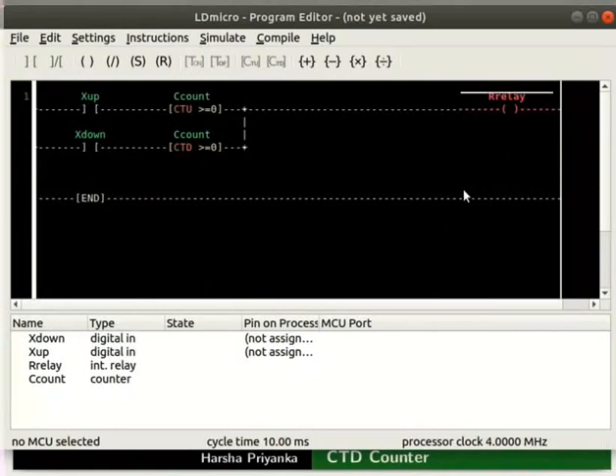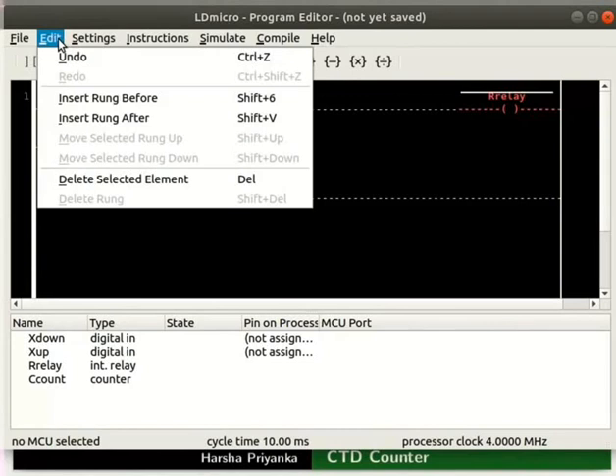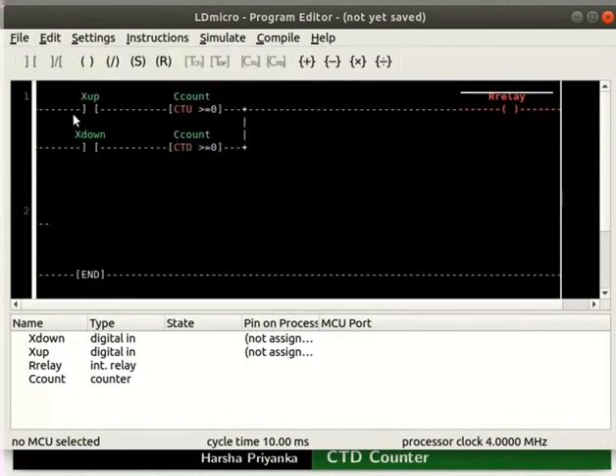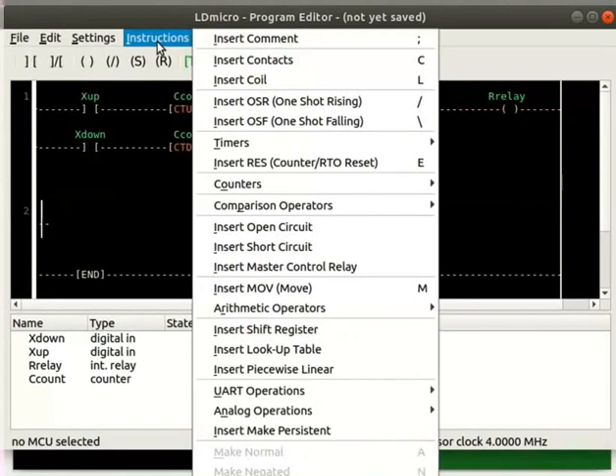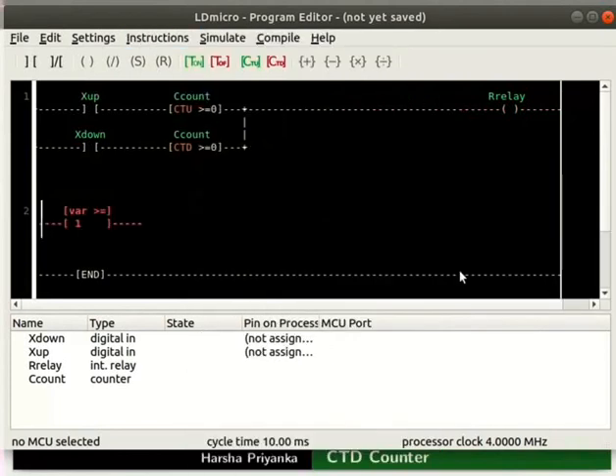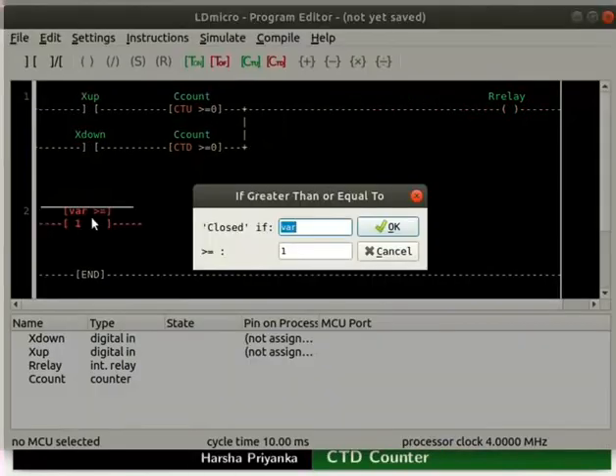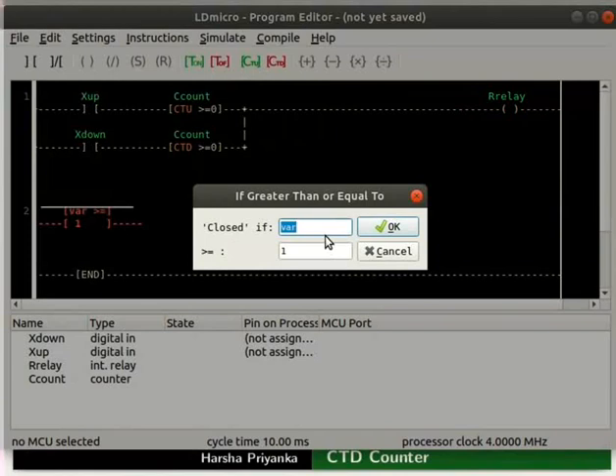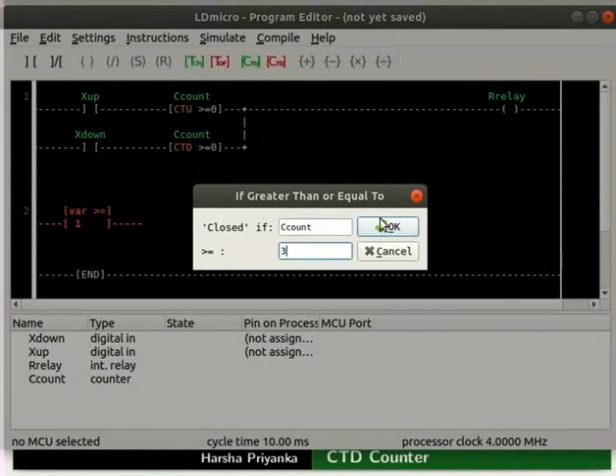Now, place a rung below as shown here. In the new rung, insert a greater than or equal to compare instruction. Double click on the compare instruction. Compare ccount variable with 3. That is, in the closed if column, enter ccount. In the greater than or equals to column, enter 3. Click on the OK button.